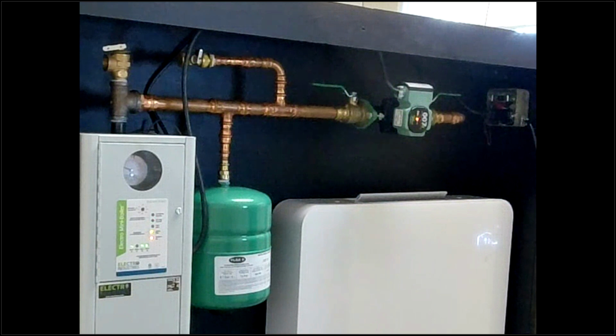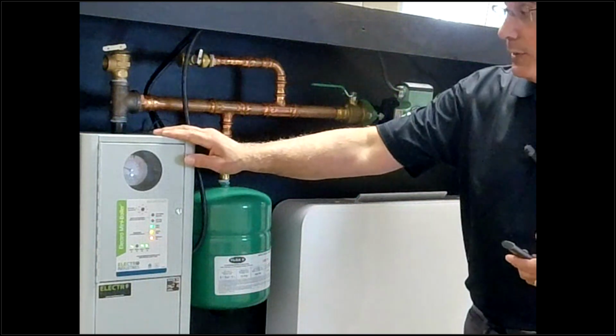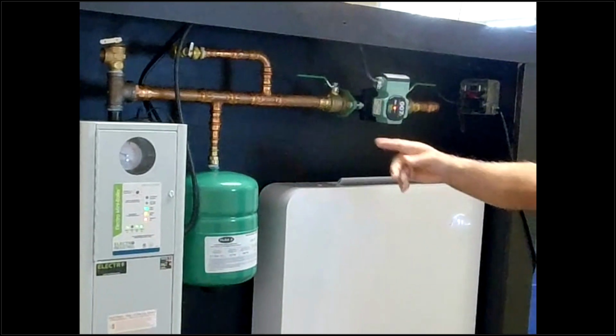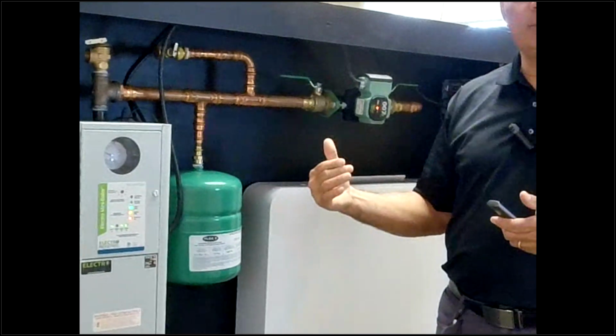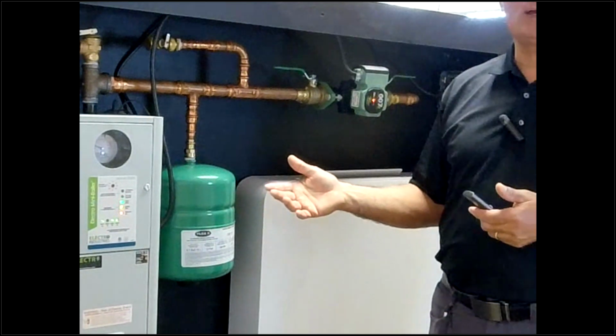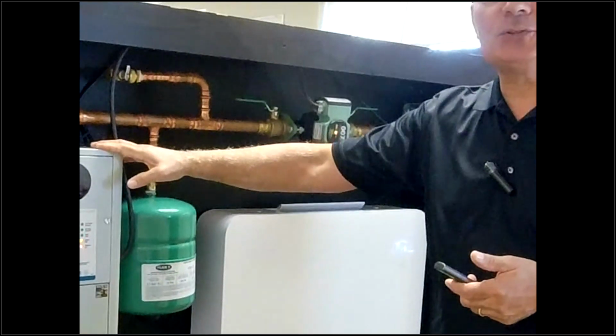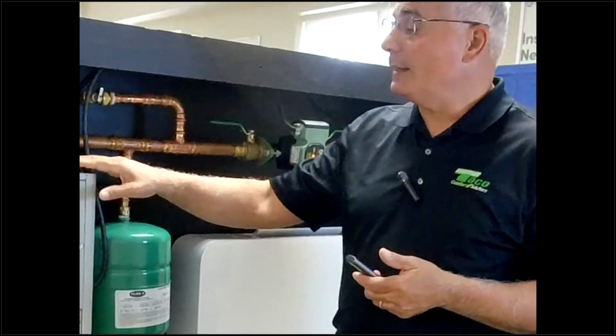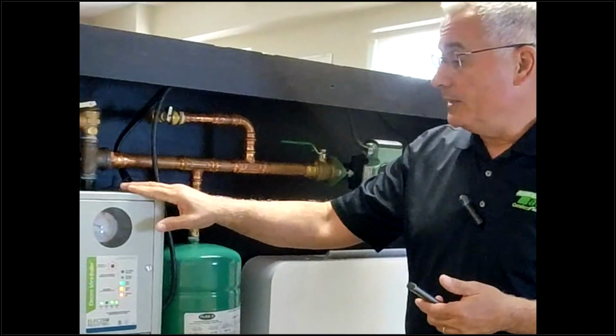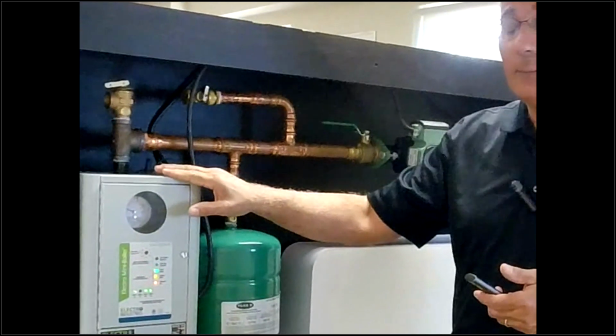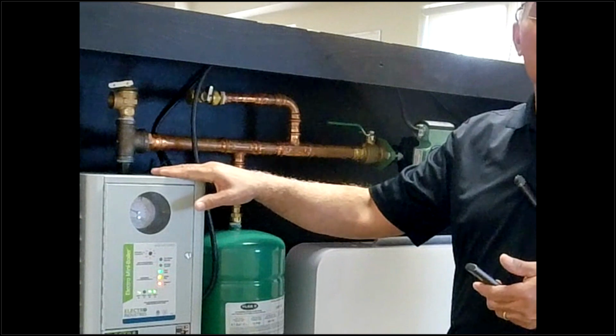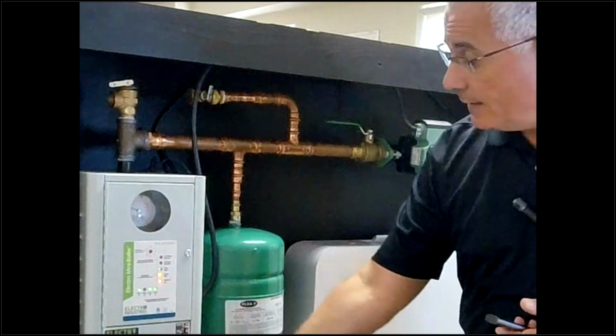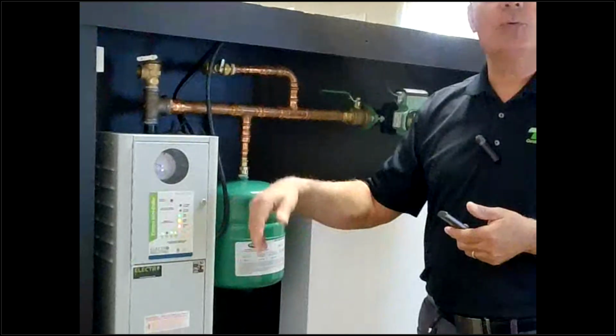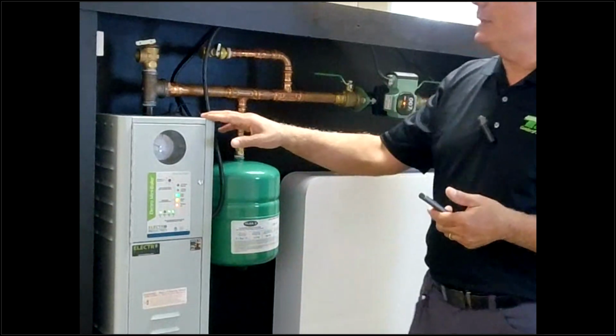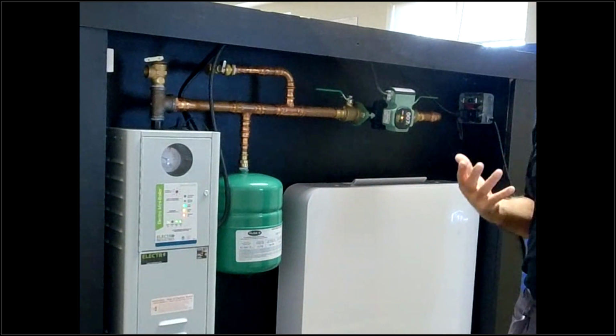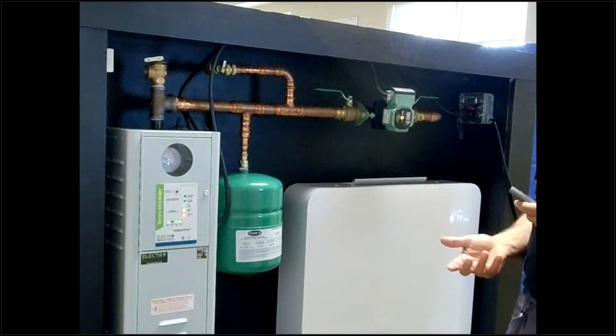So for this small zone here, I've got an electric boiler, and you'll notice that there's no special piping. This is just one supply out, one return back, because it's not a condensing product. So I can dial in whatever temperature I want here. I do have the ability on the majority of these boiler sizes from a company called Electro, where I can set a heating curve, so it's going to outdoor reset. I do have a chamber in here with an element or two, depending on the size, and the control in here will pulse power to the element based on outdoor temperature and system demand.